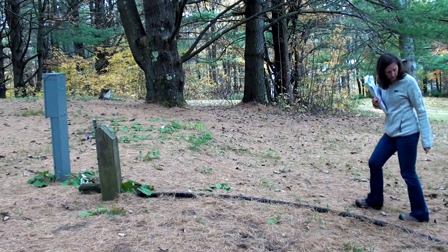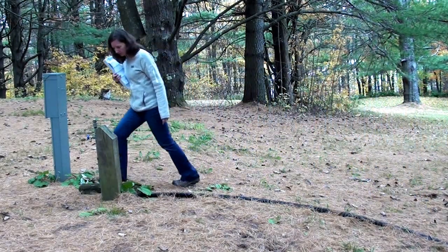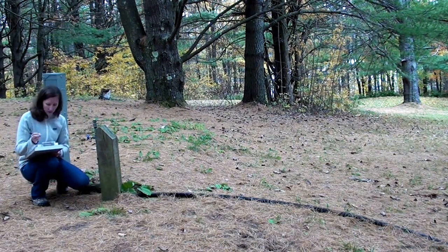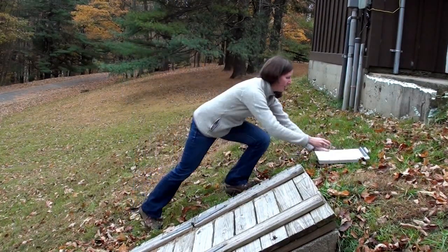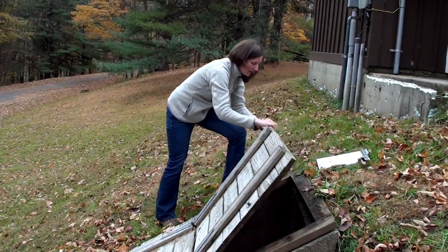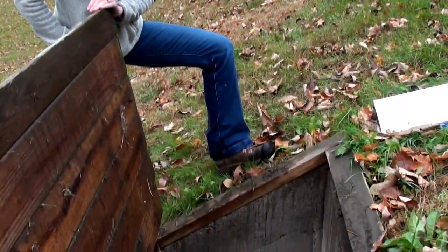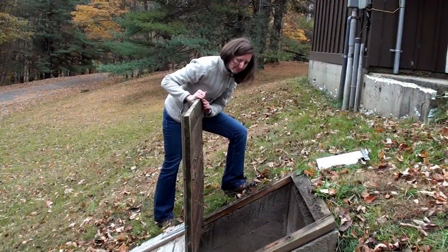From this point, we recommend, to the extent possible, walking or driving the distribution system, looking for signs of leaks, disturbance, changes, or anything out of the ordinary. If there are vaults with valves, PRVs, meters, or other appurtenances in the distribution system, make sure that they are drained and don't contain standing water, show signs of flooding, or have submerged equipment.